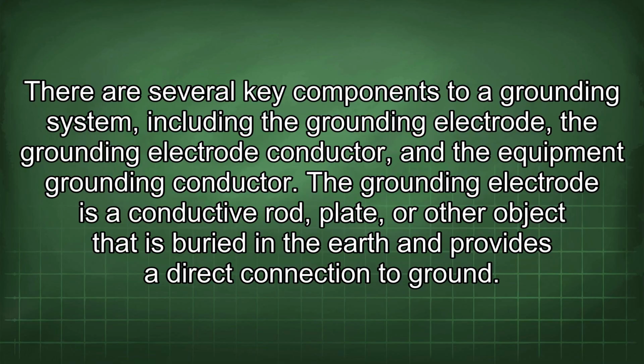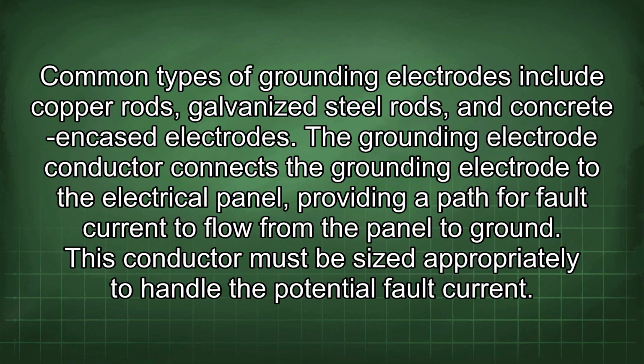There are several key components to a grounding system, including the grounding electrode, the grounding electrode conductor, and the equipment grounding conductor. The grounding electrode is a conductive rod, plate, or other object that is buried in the earth and provides a direct connection to ground. Common types of grounding electrodes include copper rods, galvanized steel rods, and concrete encased electrodes. The grounding electrode conductor connects the grounding electrode to the electrical panel, providing a path for fault current to flow from the panel to ground. This conductor must be sized appropriately to handle the potential fault current.